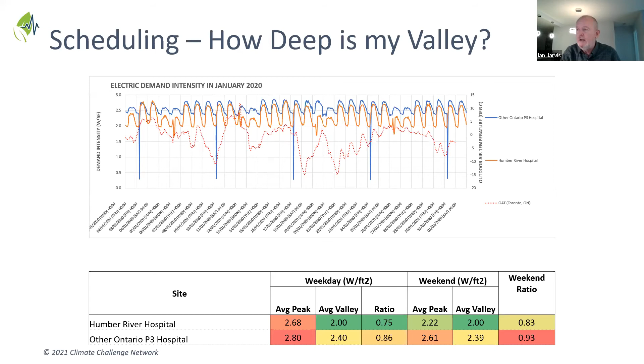That's low static fan design, that's lighting. Look how deep the valleys are. This is only the electricity use, the fan power, the good lighting controls, but the effect is that the biggest part of the difference lies in the fact that this hospital is scheduling more efficiently and effectively than anybody else.